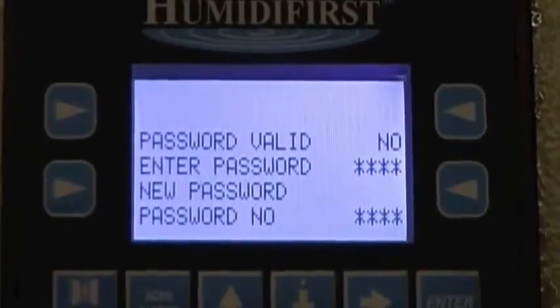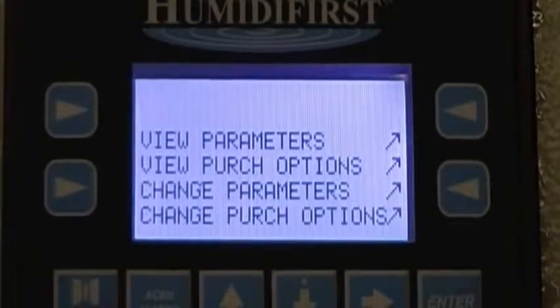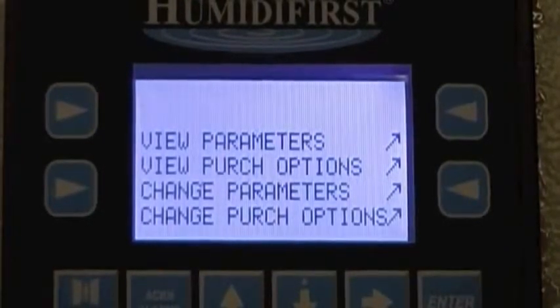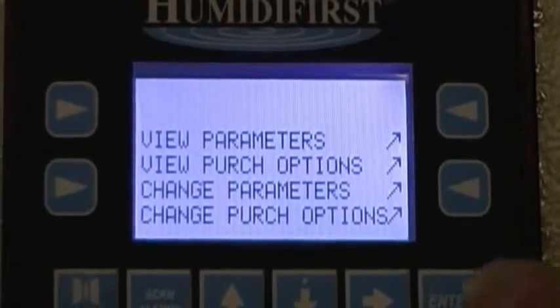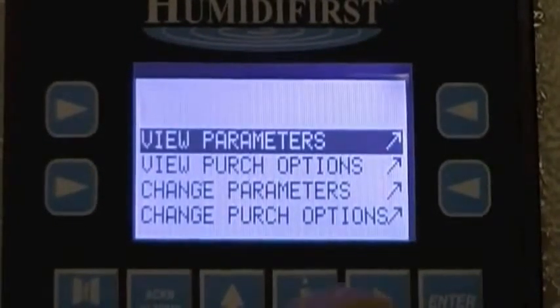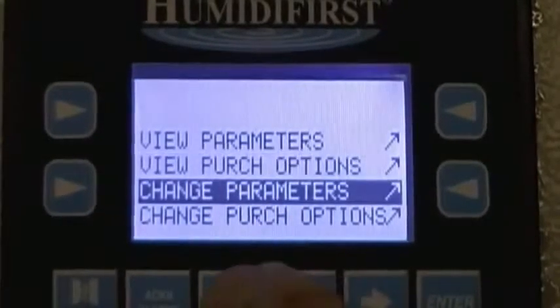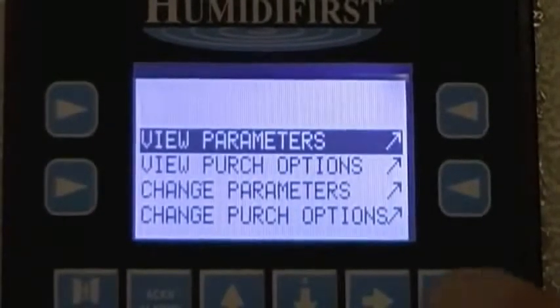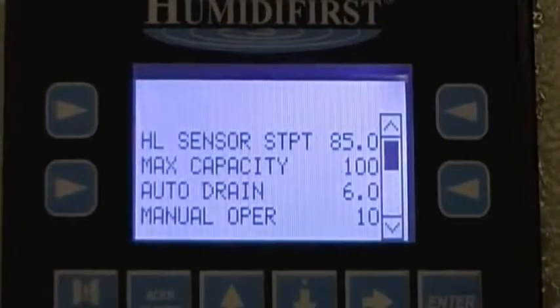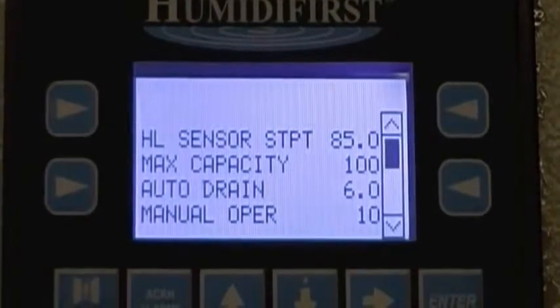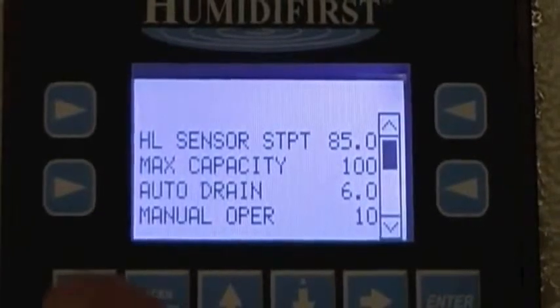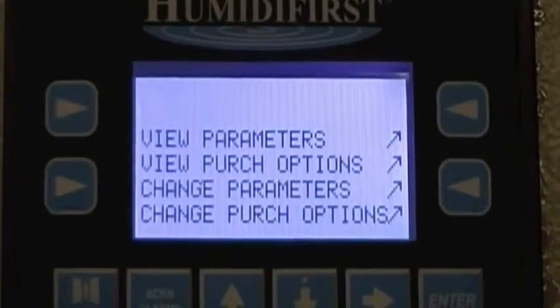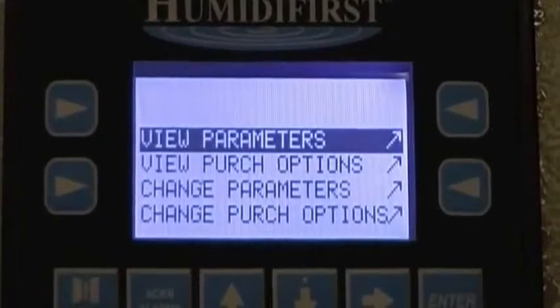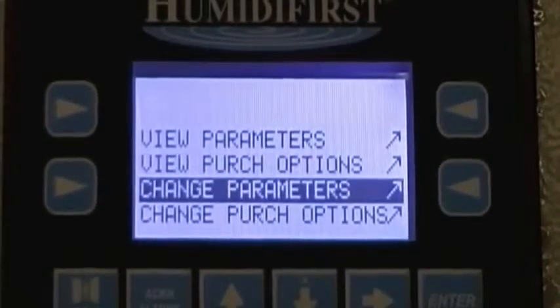Button number 2 is set points. This allows you to view parameters, view purchase options, change your parameters, and here at the factory we can change your purchase options. Upon entering the screen, you must press enter to bring up your highlight, and you may now navigate the menu. Pressing enter on view parameters will show you your set points as they currently are. If you'd like to change these set points, press escape to return to the set points menu, press enter to bring up your highlight, scroll down to change parameters, and press enter.